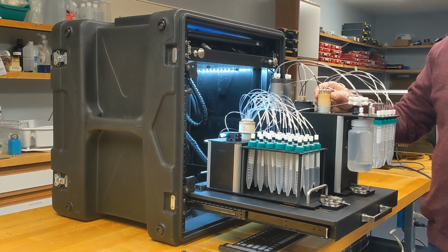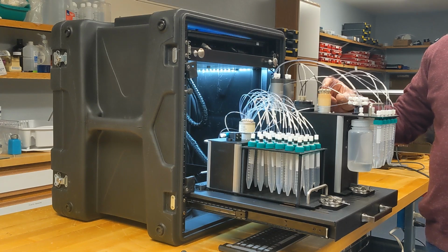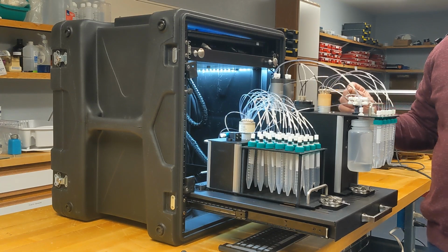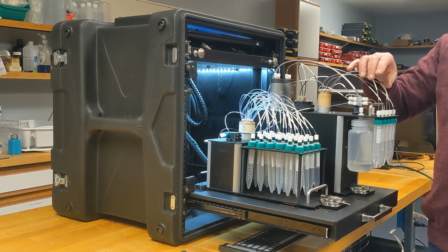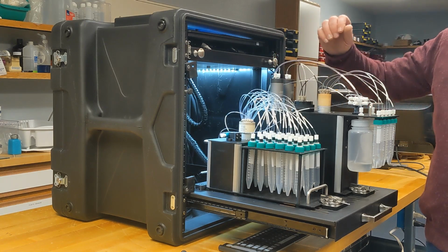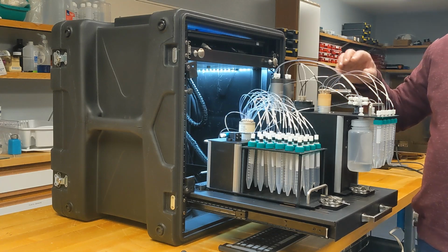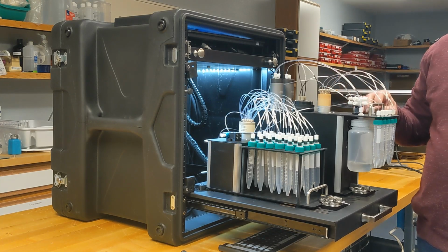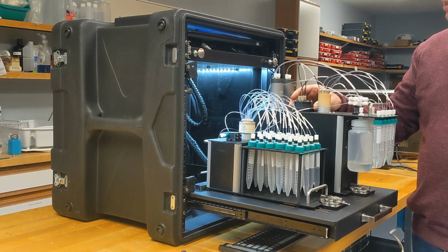Behind that is a multi-position selection valve. This valve has a common central port, and it's surrounded by additional ports that allow you to draw solution from these vials or from the sampling system. Send waste solutions off to the waste. Behind that is the detector itself.